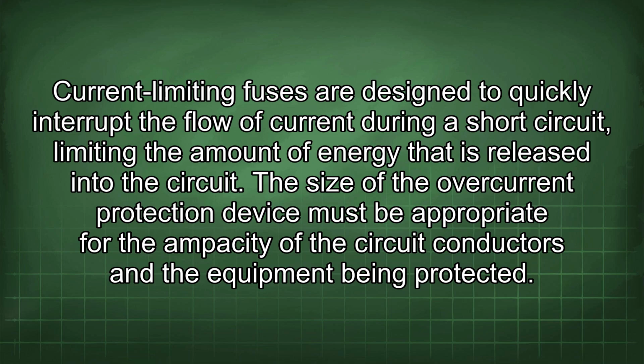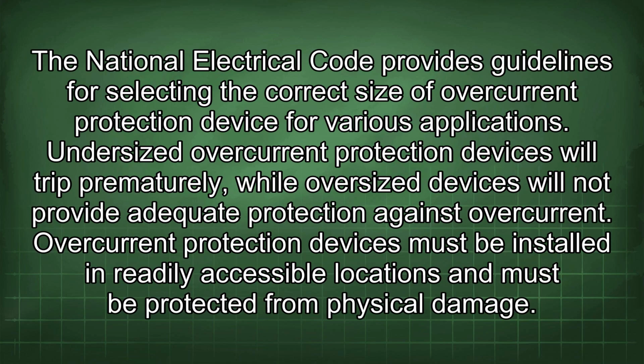The size of the overcurrent protection device must be appropriate for the ampacity of the circuit conductors and the equipment being protected. The National Electrical Code provides guidelines for selecting the correct size of overcurrent protection device for various applications. Undersized overcurrent protection devices will trip prematurely, while oversized devices will not provide adequate protection against overcurrent.